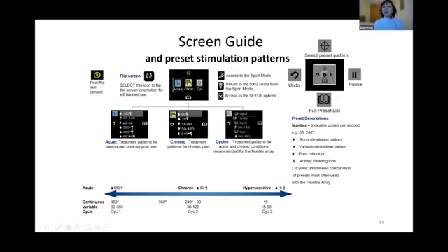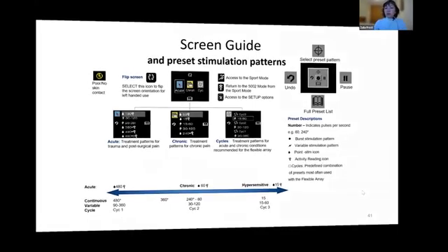So what happens if you mix these two boxes and you didn't do it right? Well, you might not get a result. So if you use low, not enough energy presets with acute, you may not get pain relief. And if you use very high packed energy settings with chronic, you can create unnecessary aggravation. So this is just to help you to understand it this way.